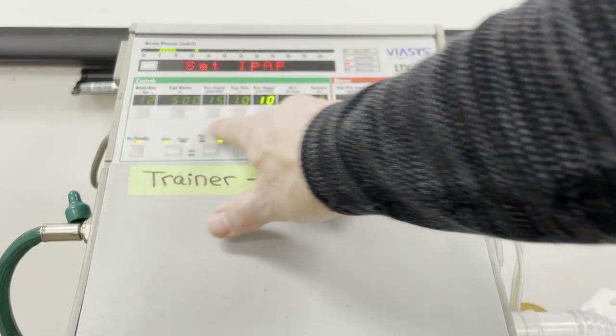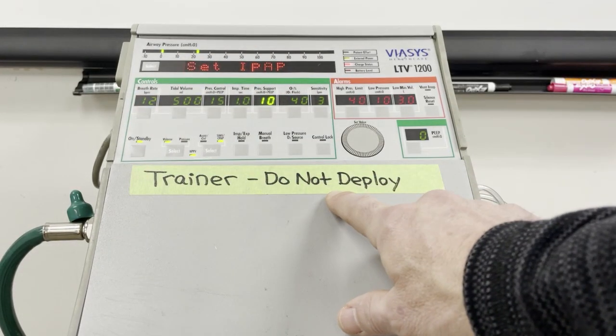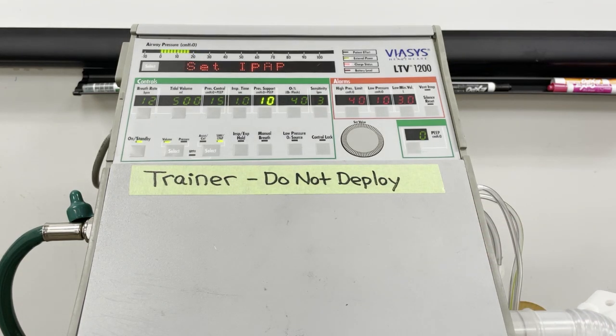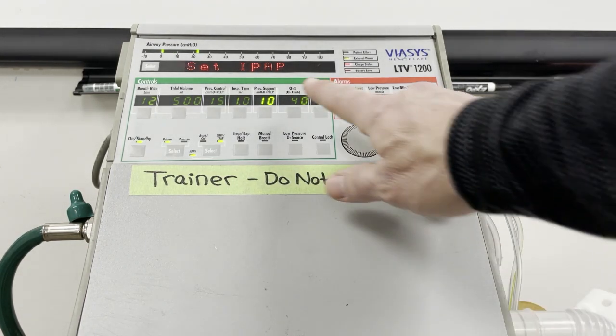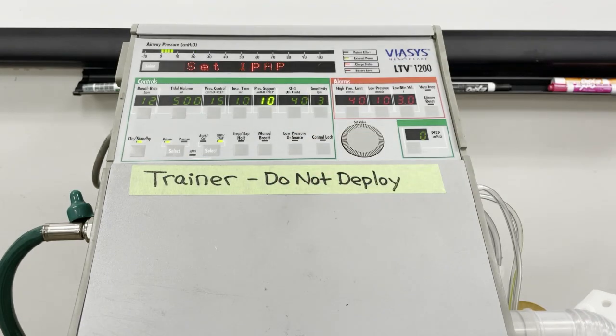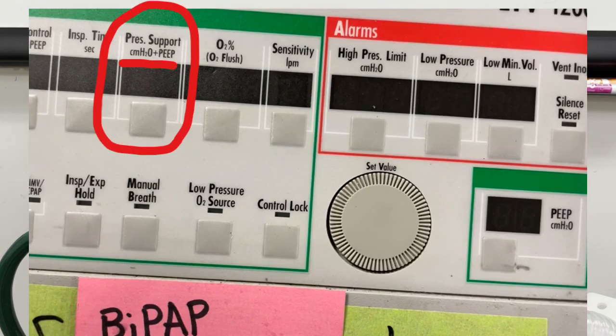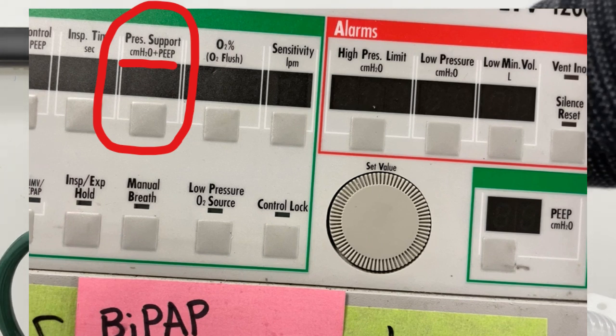You will notice the other settings on the vent have dimmed out, except for the pressure support field. This is where you will set the IPAP value. Here's the trickiest part of BiPAP on the LTV. Let's say you were given a BiPAP setting of 15/8. Following those directions, you might plug in a 15 in this field. Makes sense, right? But look closely at the pressure support setting.